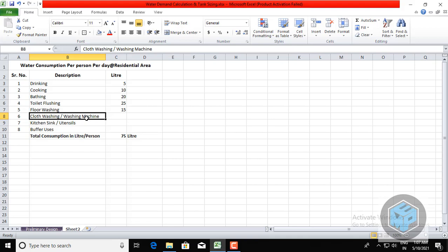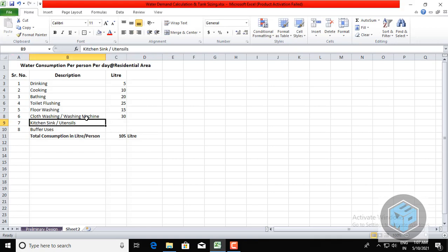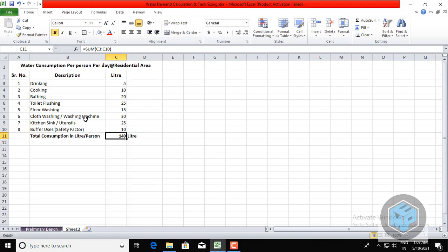For cloth washing or a fully automatic or semi-automatic washing machine, 30 liters of water is used. For the kitchen sink or utensils, 20–25 liters. A buffer or safety factor of 10 liters is also included. The total water consumption per person per day comes to 140 liters.